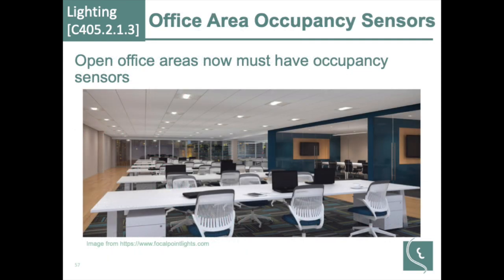This is an example of open office area lighting sensor. You can imagine if you had some lighting sensing control over by the light switch and someone was over here in the corner, they'd be a little annoyed by the light shutting off on them while they're trying to work. So open office plans in the past were exempt for that reason. Now they're just broken up into small sections so that each section can be controlled.